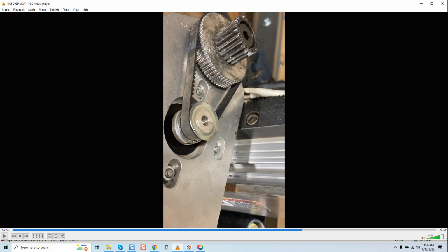Once again, my guys using rack and pinion to all these moving parts. We have a pulley system here. We don't know how the actual teeth are on here. We don't know how the tension is on this belt. You got to go through the rack once again, double check, make sure there's no surface rust forming. The tolerance on the rack is good. The bolts are right. There's no vibration issues.